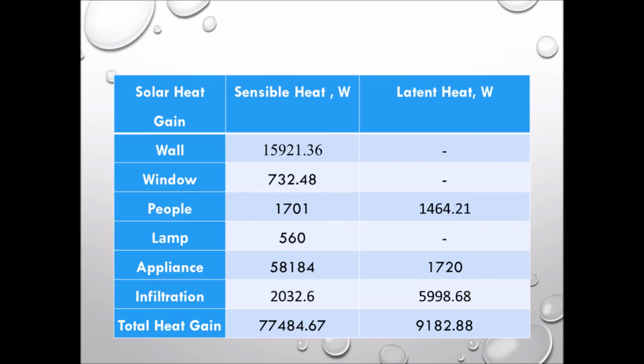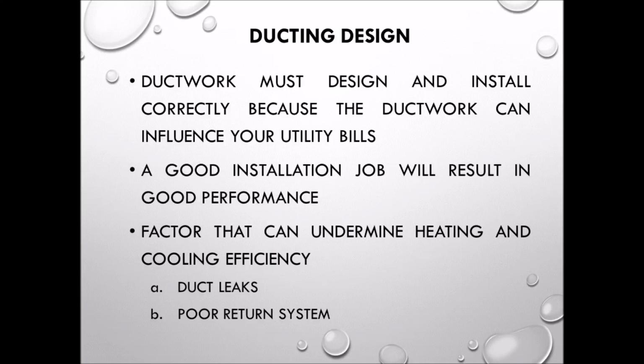This is the summary for the first, second, and third floor. The total sensible heat for the first, second, and third floor is 24,053.3, while the total latent heat is 7,300.2. The function of ducting is to channel or direct the air to the place where the conditioned air is needed.